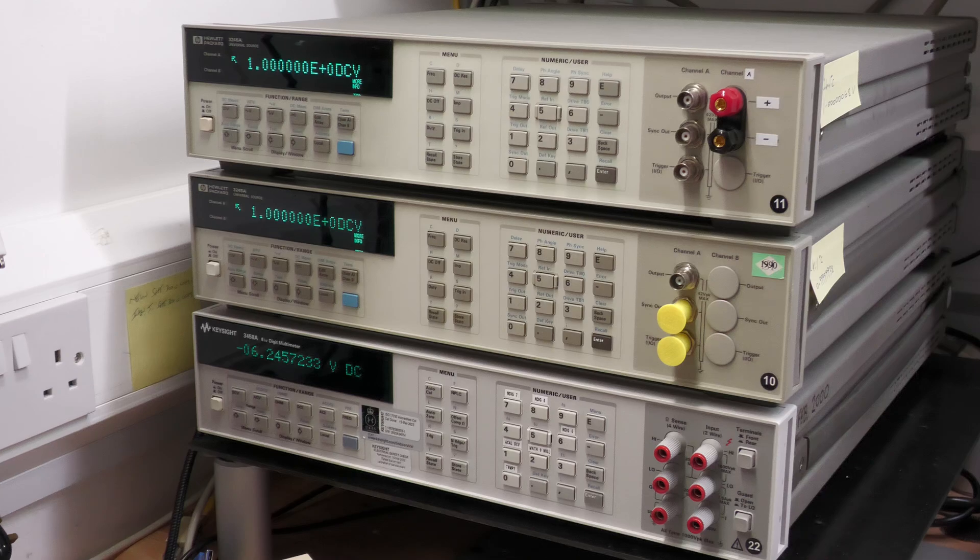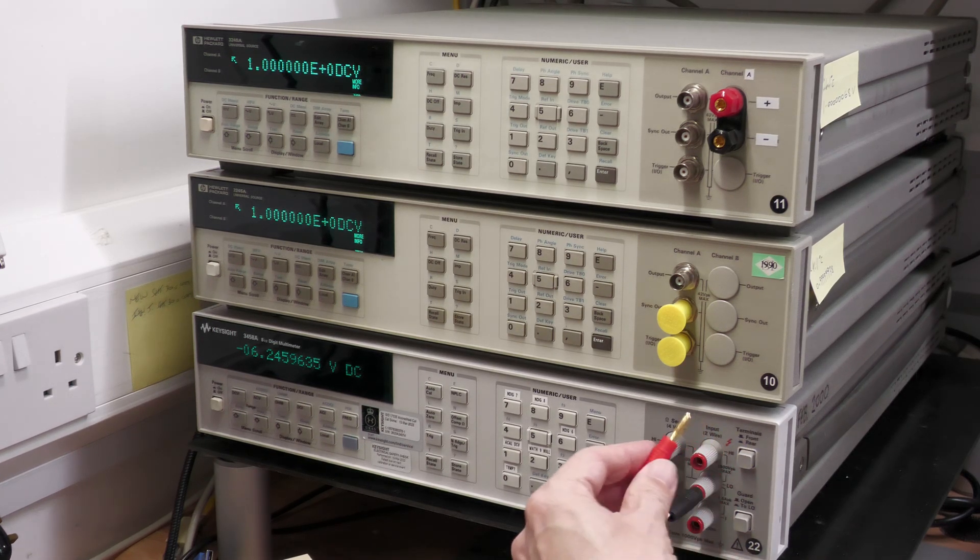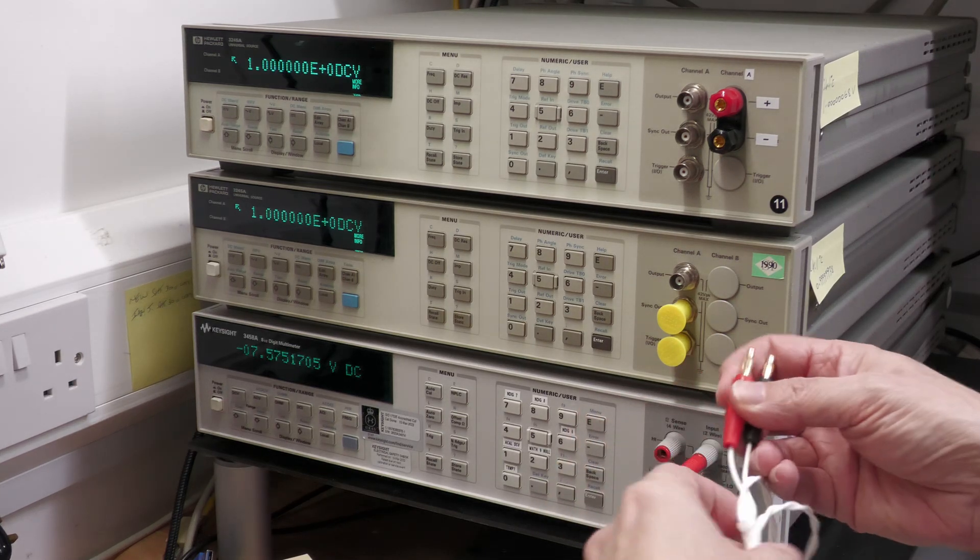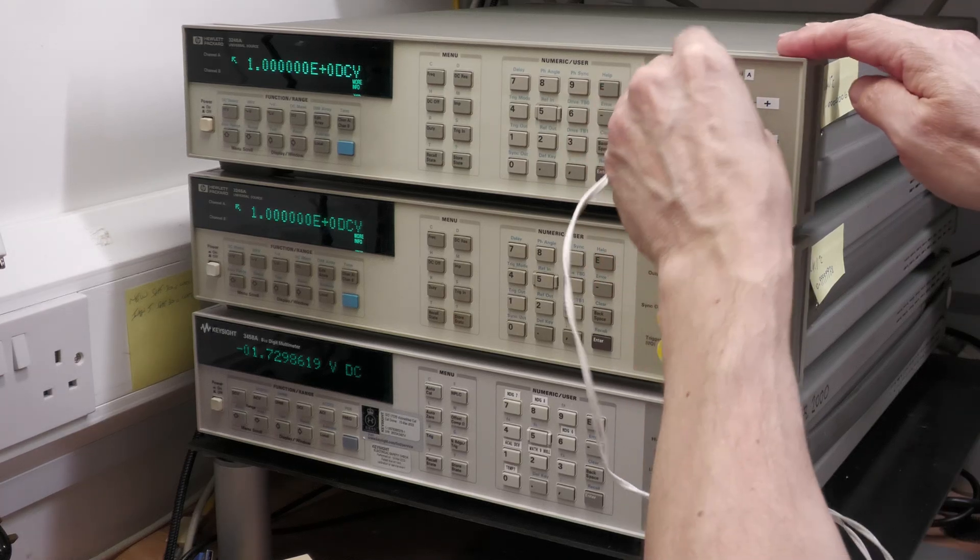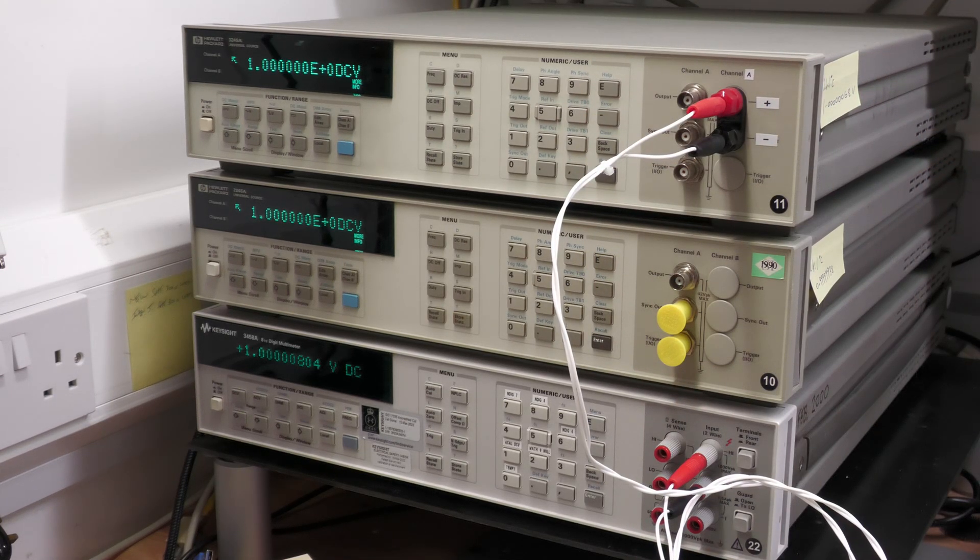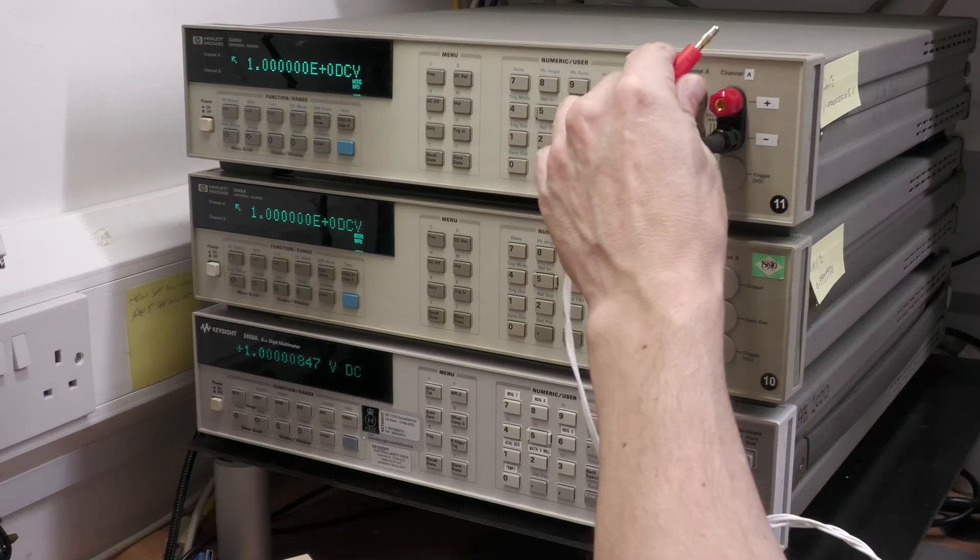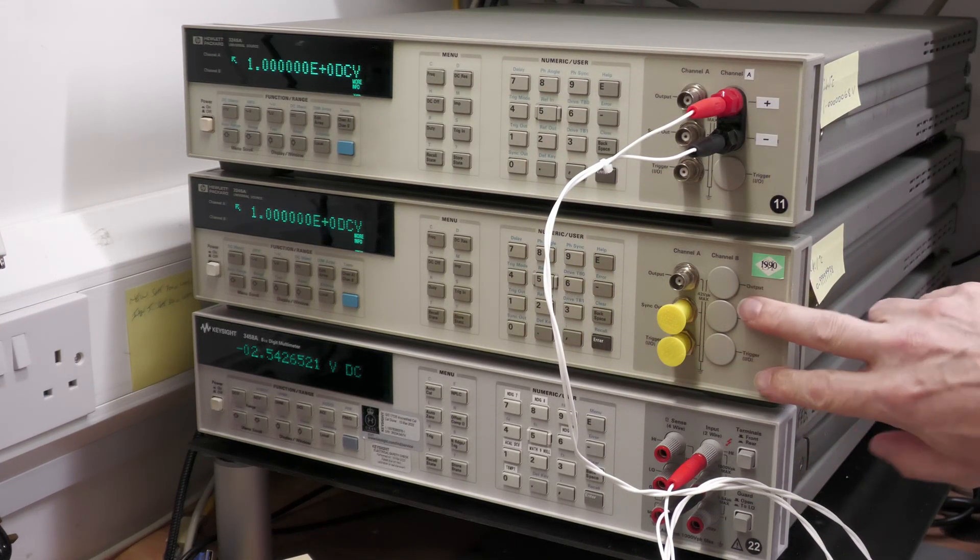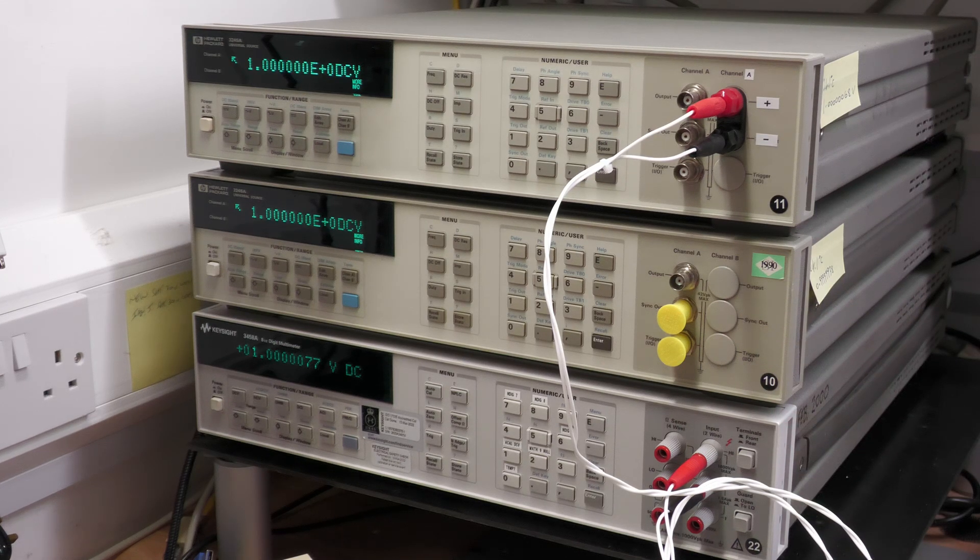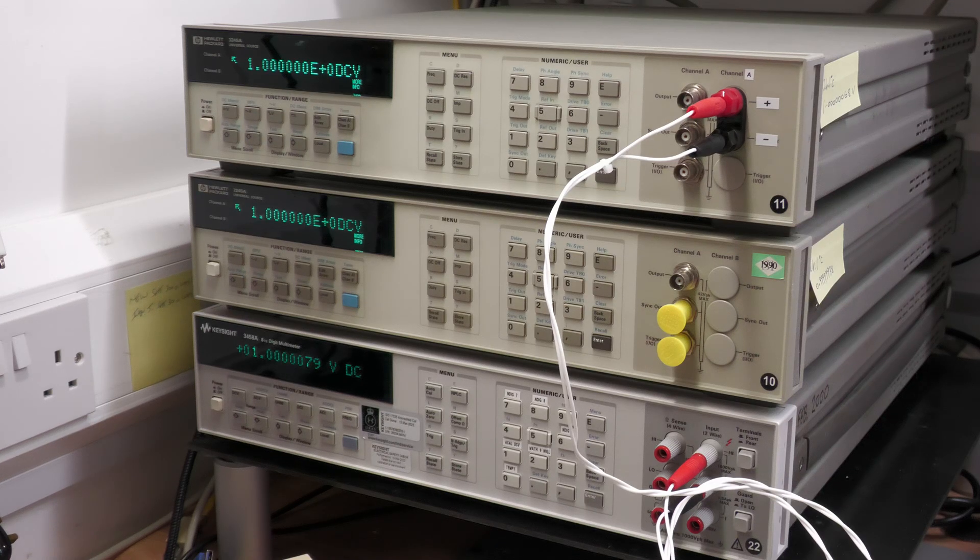Okay this is just a simple unshielded PTFE cable. Let's see how that fares. Let it settle. Okay 821. Let's pull it out. Put it back in again. And bear in mind my original 3245A here exhibits exactly the same problem. Look at that! Jump straight back down. So it's not the cable.